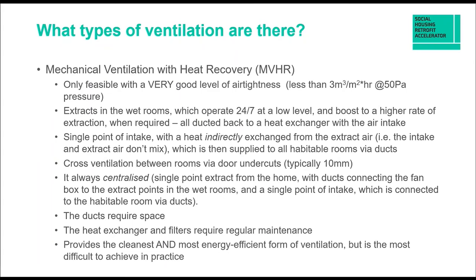The next most common solution is MVHR — mechanical ventilation with heat recovery — which can be quite tricky to implement in retrofit because it requires ducting for both extract and intake. You have to supply air into habitable rooms and extract it from wet rooms using ducting. It's more feasible if you have a loft — preferably insulated — or a cellar, crawl space, or somewhere you can run insulated ducts. It's only feasible when you have very good air tightness — around 3 m³/m²/hr at 50 Pascal or less — as by that point you're recovering enough heat that it's worth the extra cost and complexity.